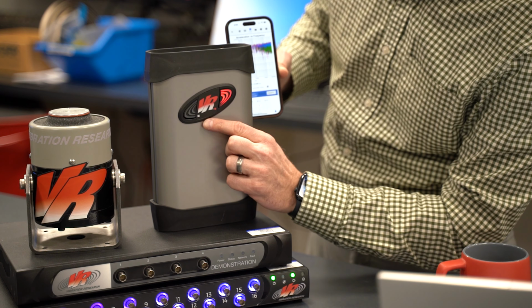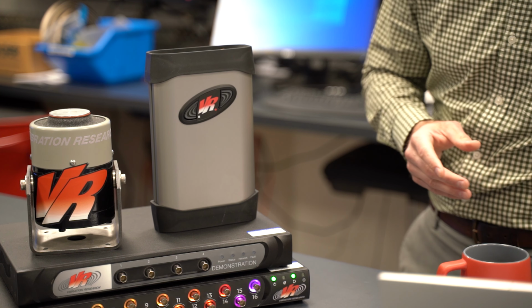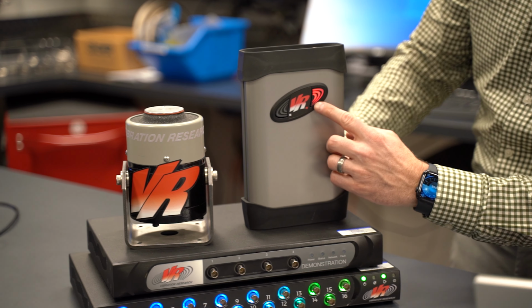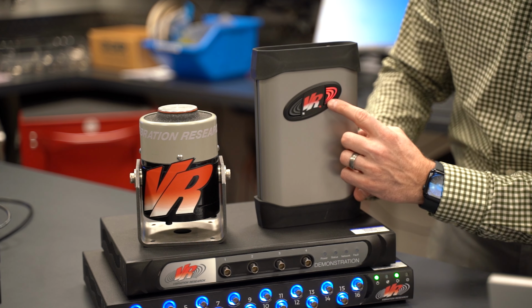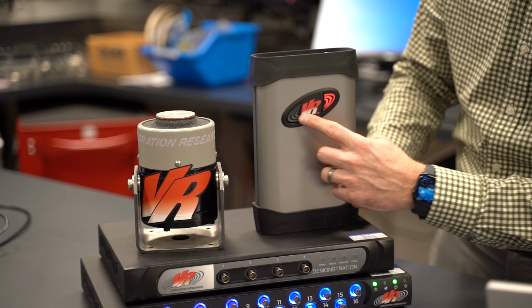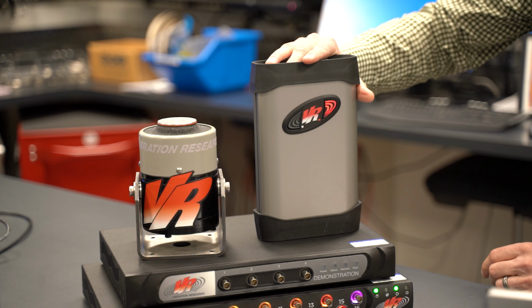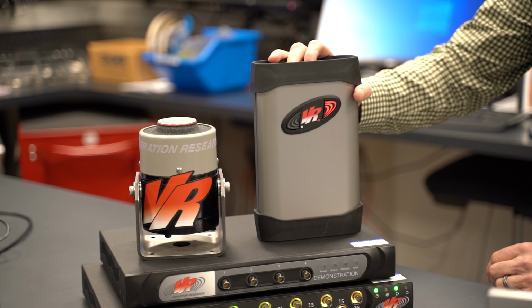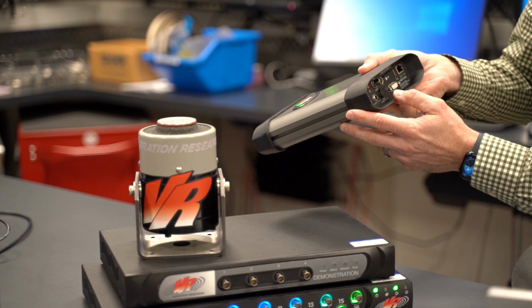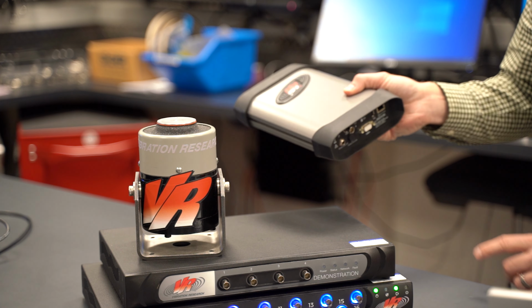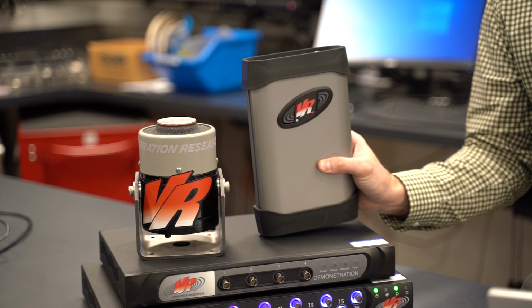The device also on the box itself has a couple of buttons at the top. Those buttons show and indicate what's happening live on the system. So this is recording. I can also stop the recording here, and it will stop my recording of the vibration test that I'm doing, and now it's paused, storing all of my data on the SD card in this case.